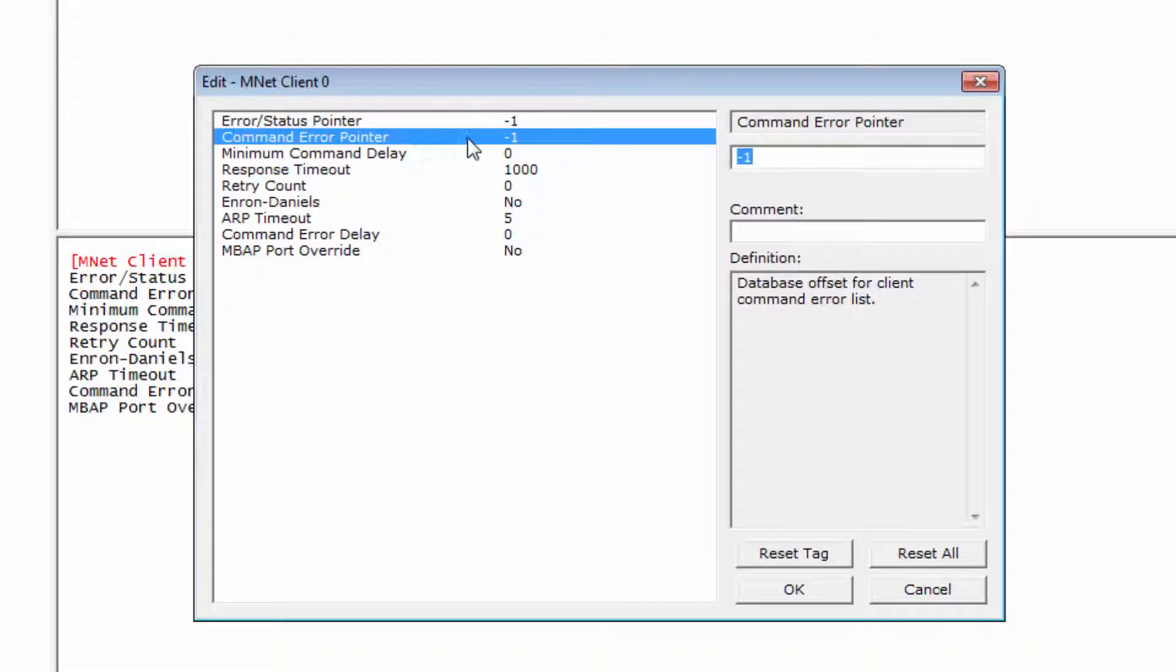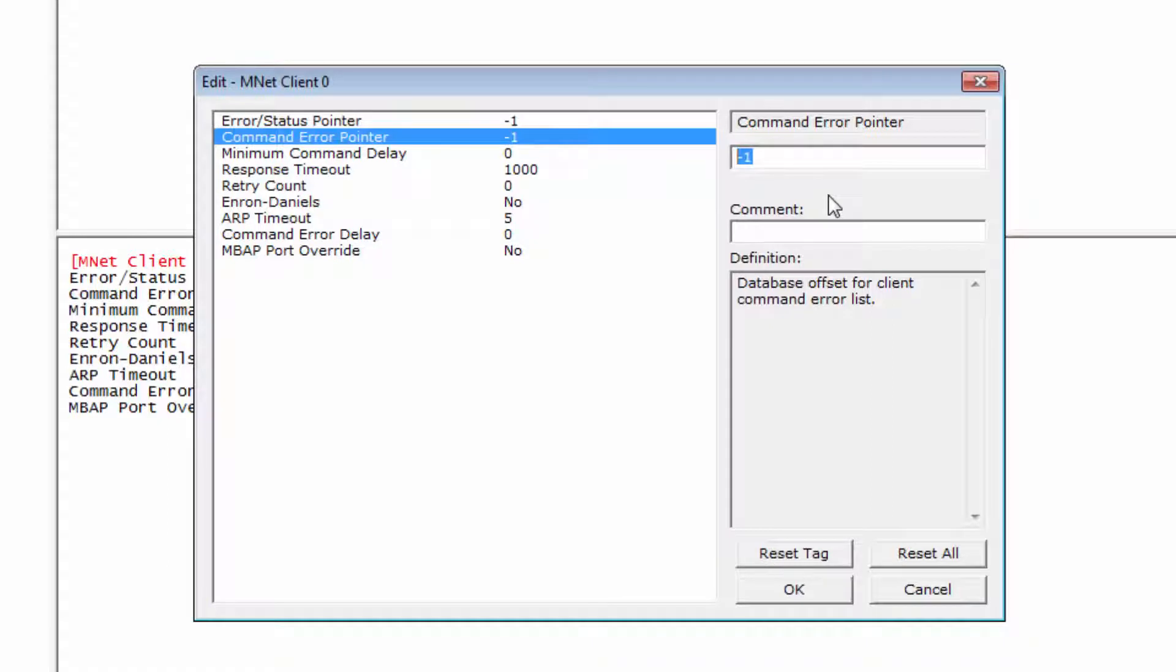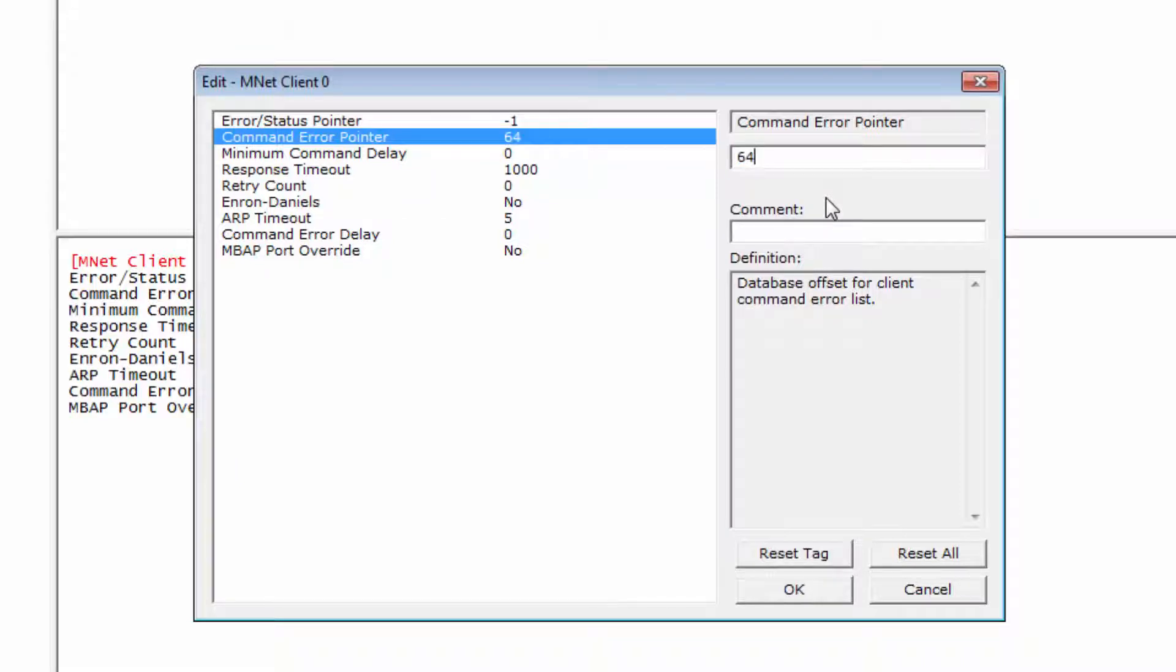The number here is the register address in the module memory where the Command Error Table will begin. As you can see, by default it has a value of negative 1 which will disable the Command Error feature. Any value other than that will define where you want to begin placing Command Error data in your module. You should take care not to assign a starting register for the Command Error Pointer where it will overwrite other data being written to the module from your program.